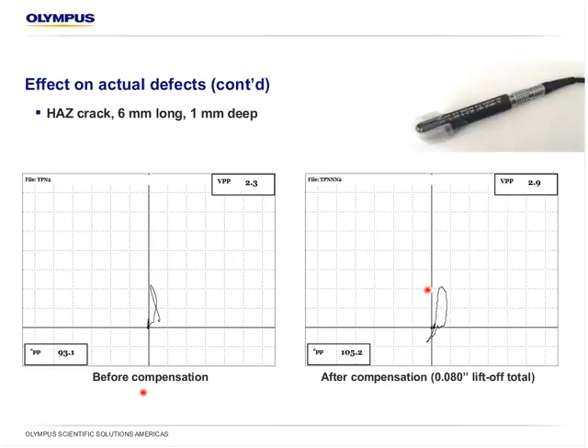And well, you might say, yeah, the signal doesn't look the same. That has more to do with the scanning than anything. But what's important is the number of vertical divisions that the signal goes. So paint removal is definitely gone with eddy current. No paint removal is needed. The surface, we can't say that it doesn't need to be prepared. It's minimal surface preparation because you need to make sure the probe can pass. If there would be some major deposits or something that prevents the probe from passing, you would need to remove it. But it's nothing like paint scraping or all that tedious process.